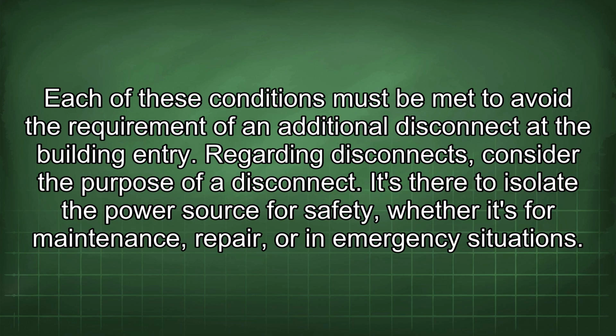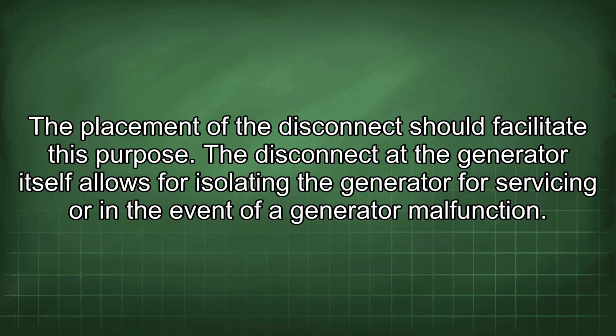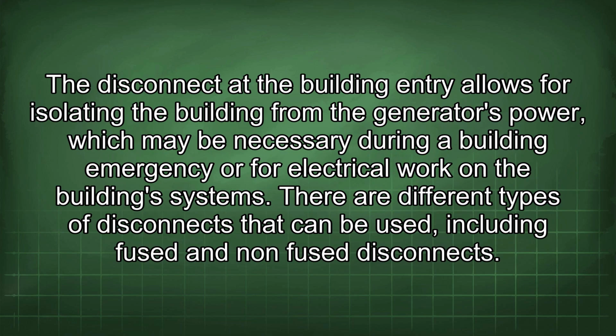Regarding disconnects, consider the purpose of a disconnect. It's there to isolate the power source for safety, whether it's for maintenance, repair, or in emergency situations. The placement of the disconnect should facilitate this purpose. The disconnect at the generator itself allows for isolating the generator for servicing or in the event of a generator malfunction. The disconnect at the building entry allows for isolating the building from the generator's power, which may be necessary during a building emergency or for electrical work on the building's systems.